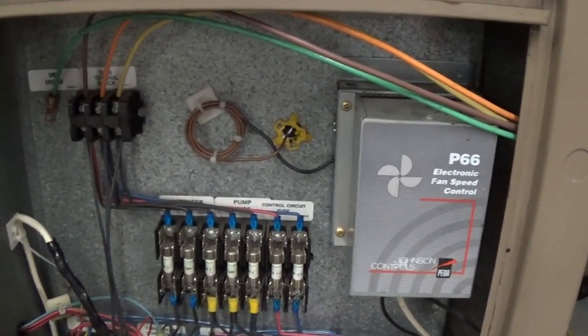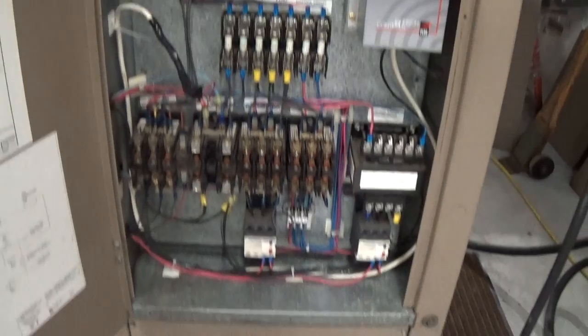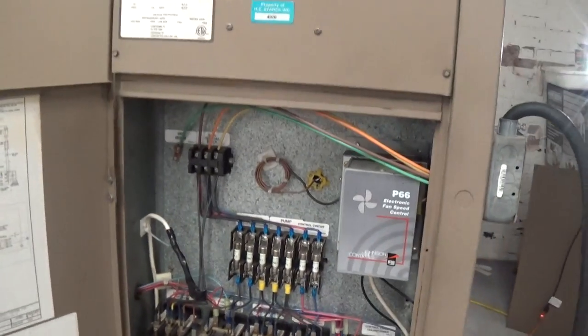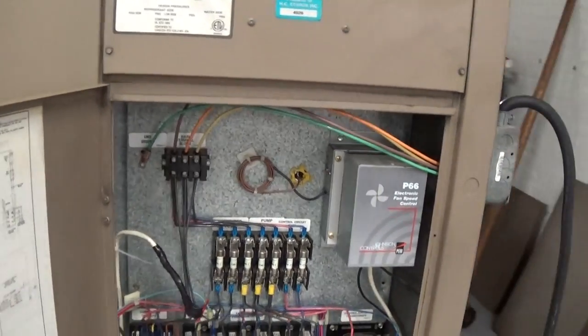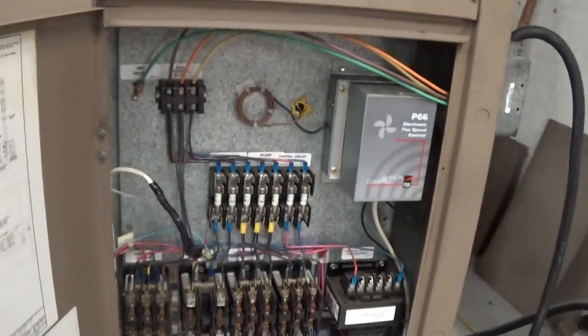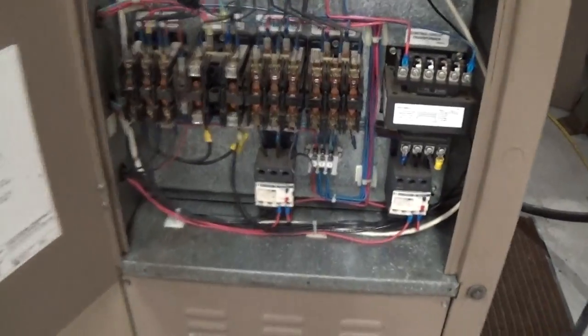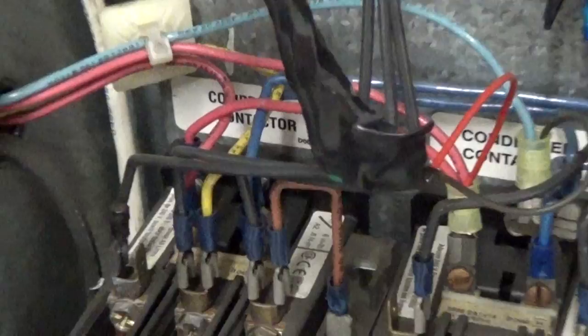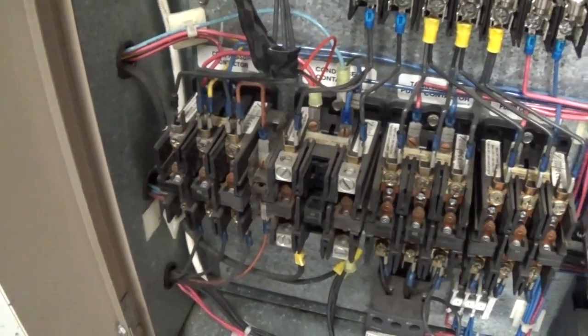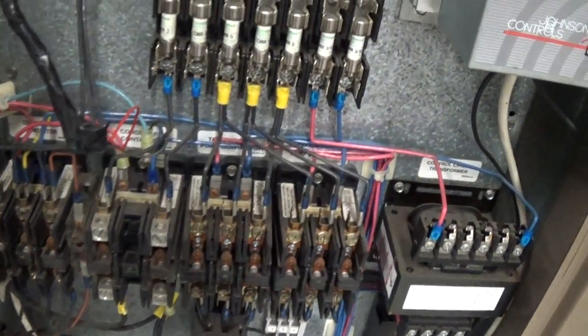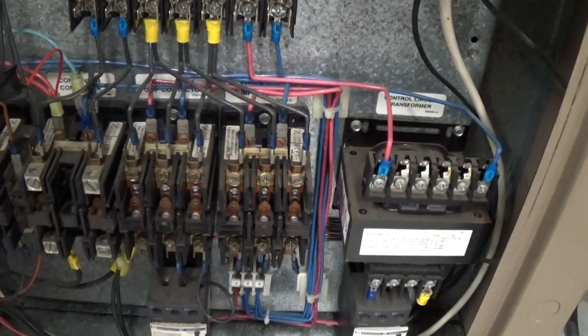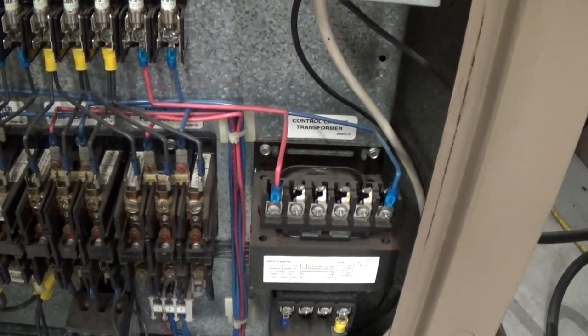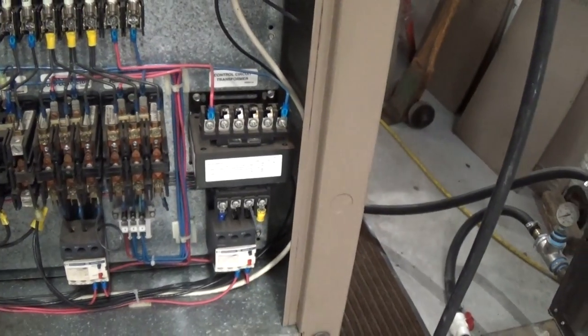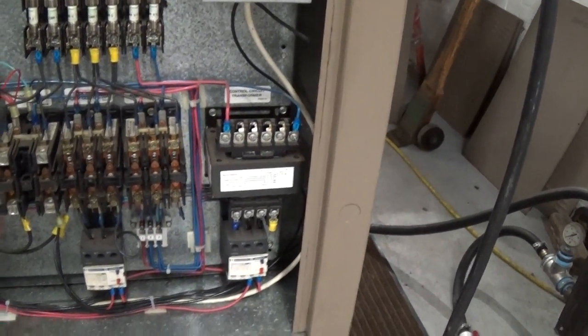That's what helps us achieve the low ambient capability for this unit to run year-round outdoor in the cold also. It is outdoor rated weatherproof, as all Drakes like this are from the factory. We have our contactors in here, and they are labeled nicely actually. Compressor contactor, condenser, tank recirculation pump, system or the process pump. This is a two pump system, and our controller transformer here also.